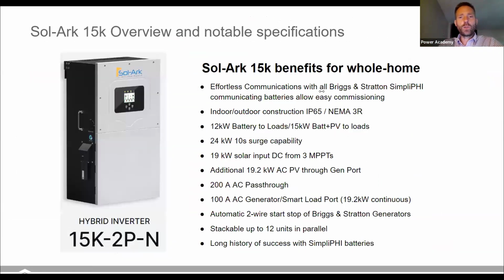uses. So some highlights of the Sol-Ark 15K is that you get effortless communication with our batteries. All of our batteries are vetted to communicate well with the Sol-Ark inverters. You can do an indoor and outdoor installation. A lot of customers will put the Sol-Ark 15K on the outside of the home just to free up wall space in the garage, etc. So it's IP65 rated, just like our batteries, NEMA 3R enclosure. 12 kilowatts from batteries to load. So you've got 12 kilowatts continuous. If you've got some solar, you can have 15 kilowatts of continuous power out of this inverter. You've got a surge of 24 kilowatts for up to 10 seconds. You can do 19 kilowatts of solar on the DC ports, 19 and a half on 3 independent MPPTs.